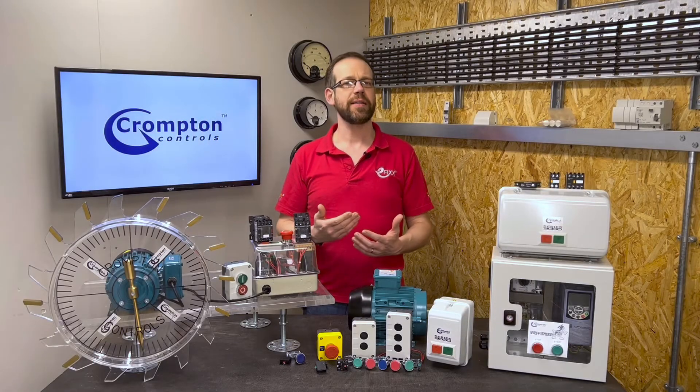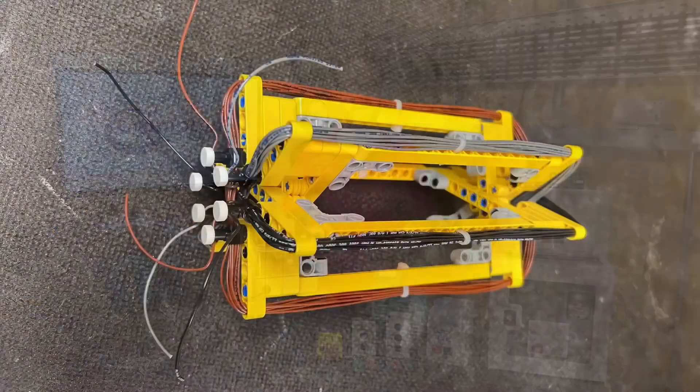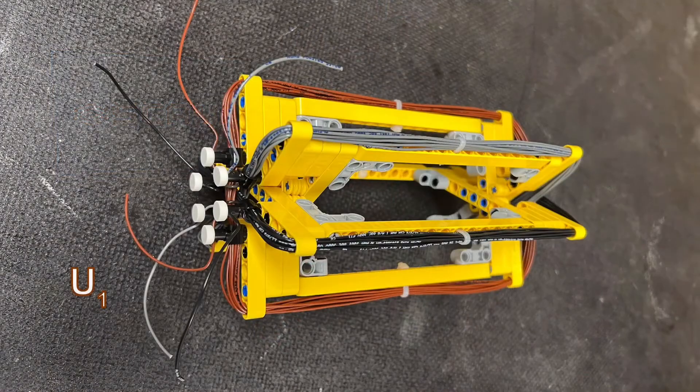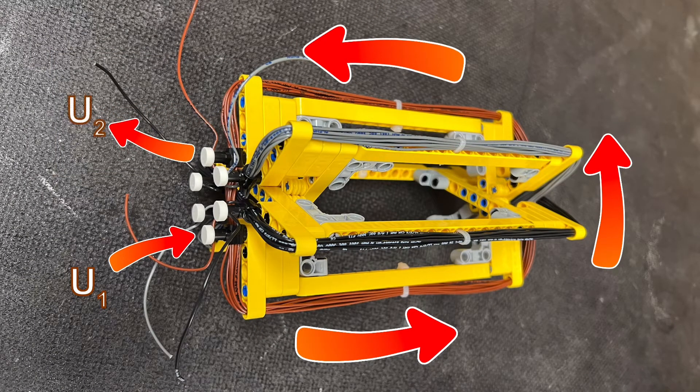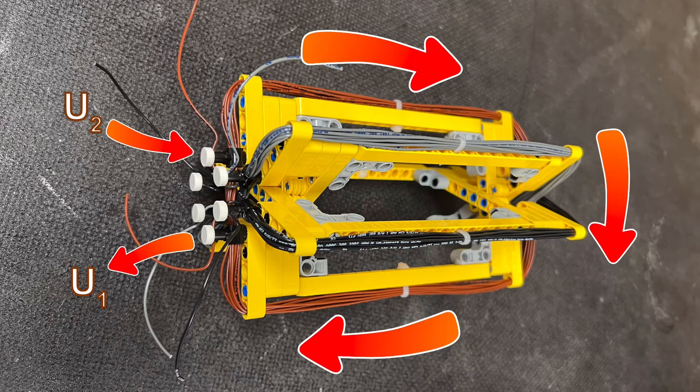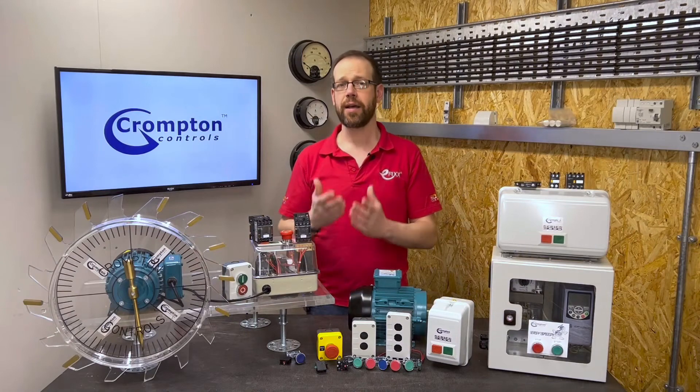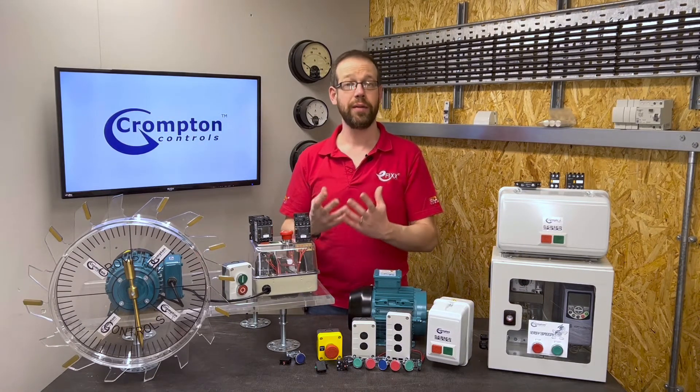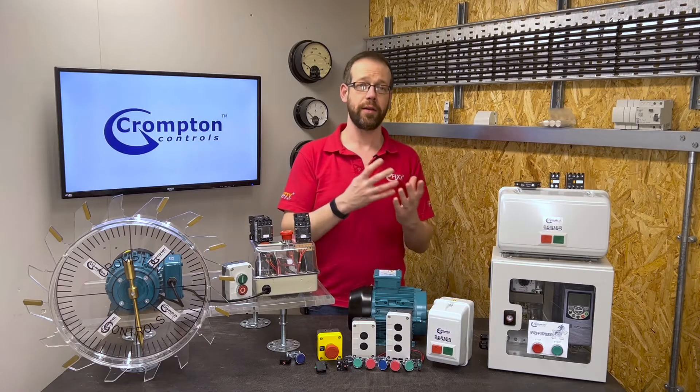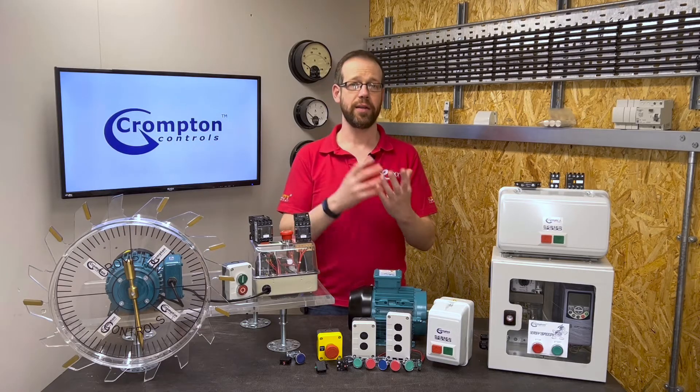That's going to be critically important in just a moment. So we're going to say that when the current is in the positive part of the cycle, it's going into the terminal marked with a one and coming out of the terminal marked with a two. And when the current goes into the negative part of the cycle, it's changed direction and goes the other way. For simplicity, we'll connect the motor in star, which means we'll connect all the wires marked two together and connect U1 to line one, V1 to line two, and W1 to line three.